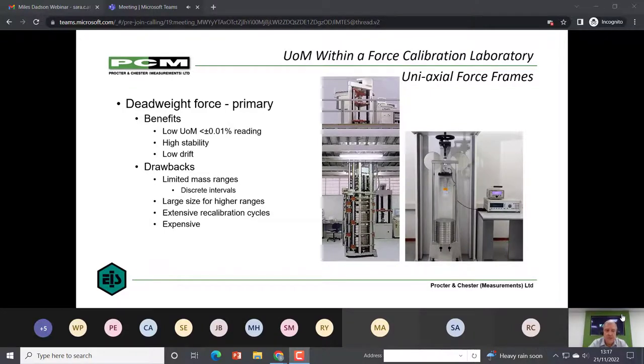But there are drawbacks. You have limited mass ranges, which means that you have discrete intervals. You can see on the left-hand image, that is a very large calibration device, and by no means is it the largest. That is around 5 meters in height. There are also extensive recalibration cycles, where you have to completely disassemble the frame and recalibrate each mass individually, and they tend to be quite expensive beasts.